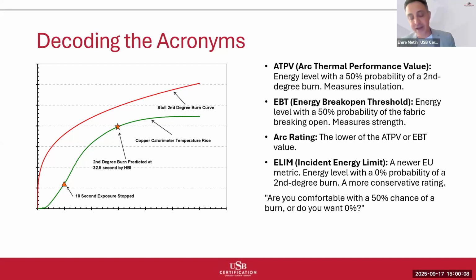ELIM, incident energy limit. This is a newer, more conservative European metric that represents the energy level with zero probability of second-degree burn, instead of accepting 50% probability, ELIM aims for no injury risk.